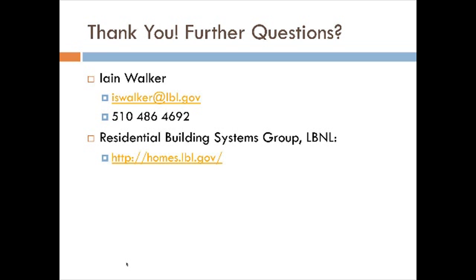Okay. So the first question I have for you: if a tight home has a balanced ventilation system, shouldn't supply air dynamically balance exhaust depressurization? I'm not exactly sure what the question is there. Yes, if you could have separate supply and exhaust fans, but not have an HRV installation, that's for sure. Or you can think about the situation where you have a supply that's operating continuously, and you turn on a bathroom exhaust fan or a kitchen exhaust fan. If it's of a similar airflow, and they will be for most homes, basically you're going from supply to balanced when you do that. That is certainly true.